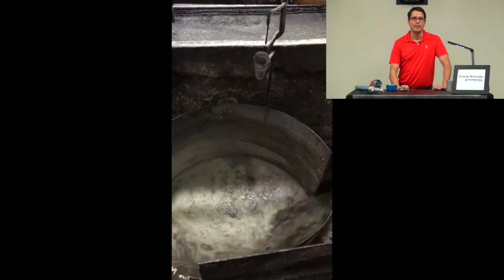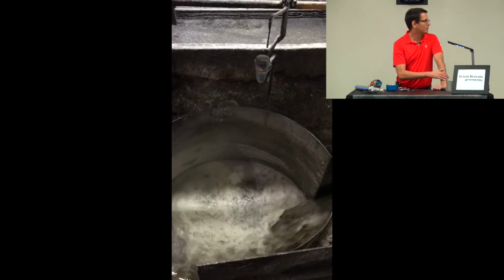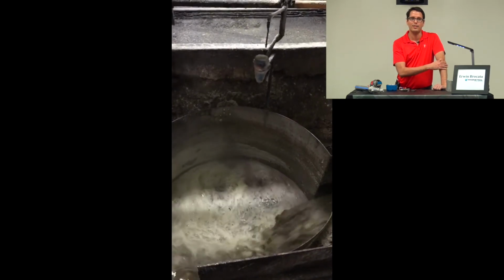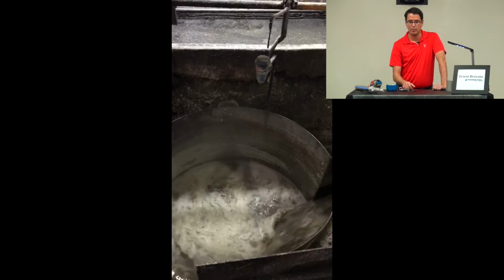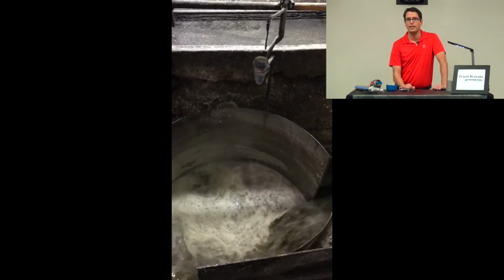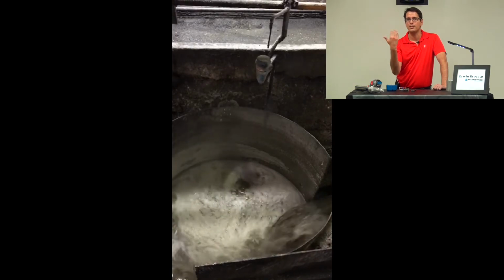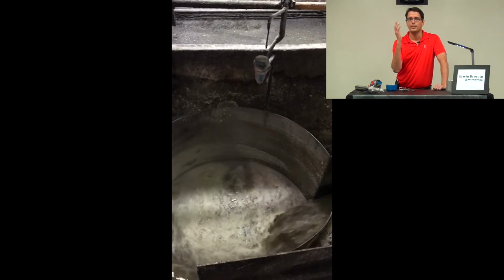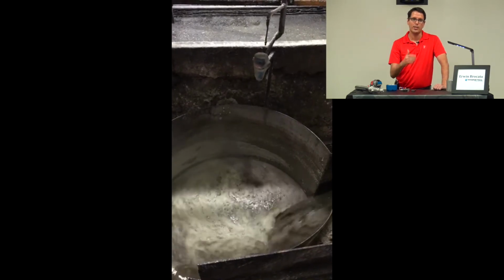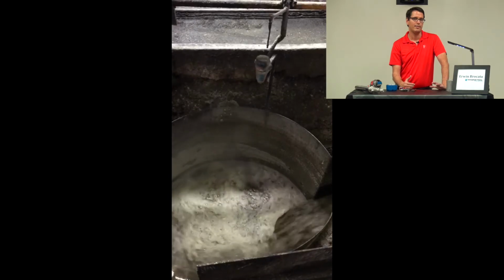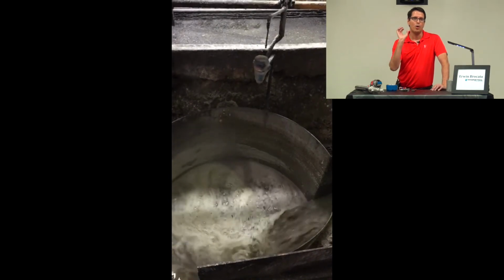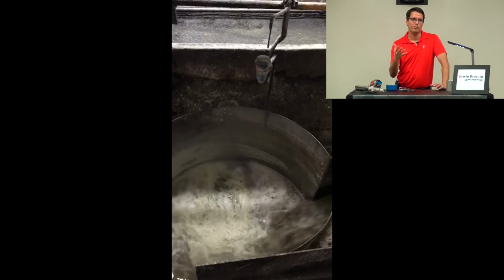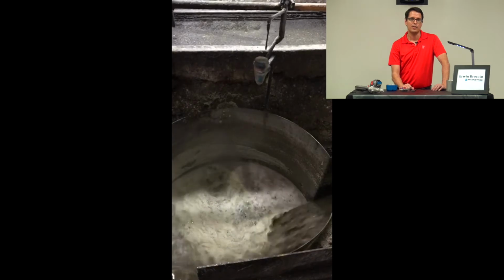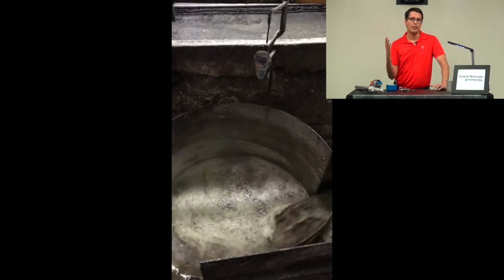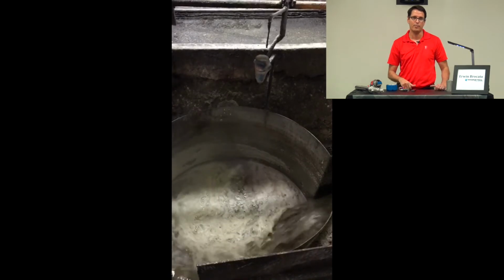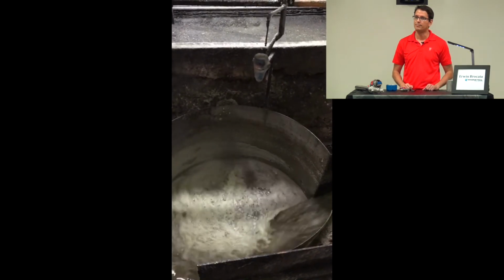Yes. This is a great example of one of these R82 devices in a sugar factory. This is in Mexico. You can see all the turbulence, all the disturbances. You can see steam coming up. You can see foam. There's actually a stream of liquid that can maybe be picked up by the device as an echo or as a level. Our representative down in Mexico was really good, and they set up this device, and it's functioning very well. So again, to Bill's point, great performance at a low cost. It's actually a pretty good solution for this kind of application. Good. Thank you.